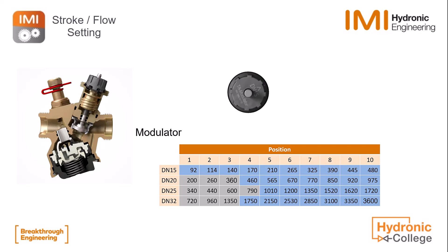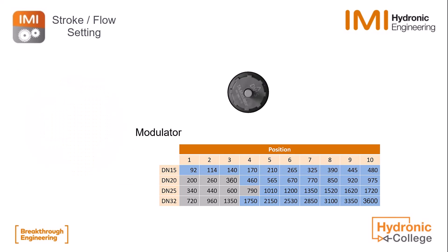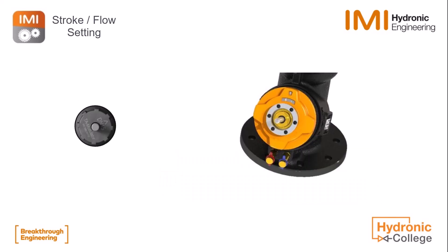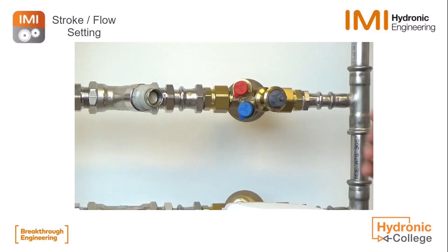So let's look at the first and easiest way to preset a modulator for a certain flow — this is the mechanical option. We set the presetting wheel to a certain position related to the flow indicated in our datasheet or selection software. After mounting the actuator, it will perform a calibration — stroke detection — and will function depending on this maximum set stroke.